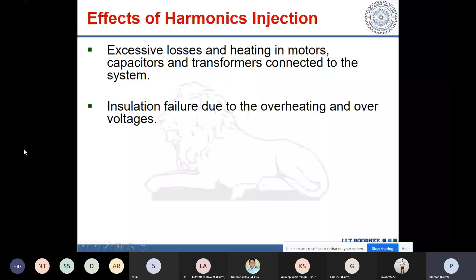In residential buildings, the main problem is the neutral current, because while doing the wiring, if the neutral wire is not properly selected, then the entire current flows through the neutral wire. Since every equipment draws third harmonic current, all those triplens will flow through the neutral. The neutral gets overheated. Maybe after some time the neutral opens, and then there will be voltage fluctuation. Because of these harmonics, your equipment may malfunction. If the neutral is not properly grounded, your computers and other things may not function properly.